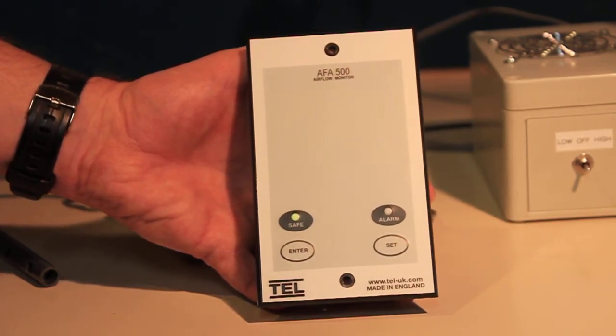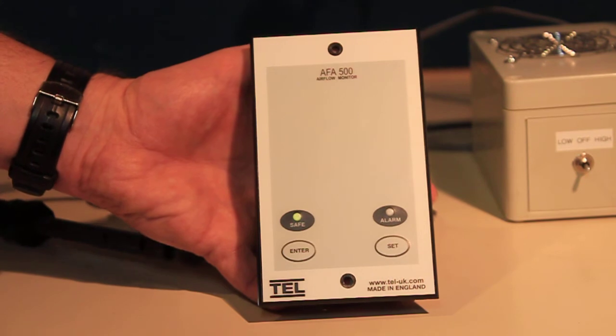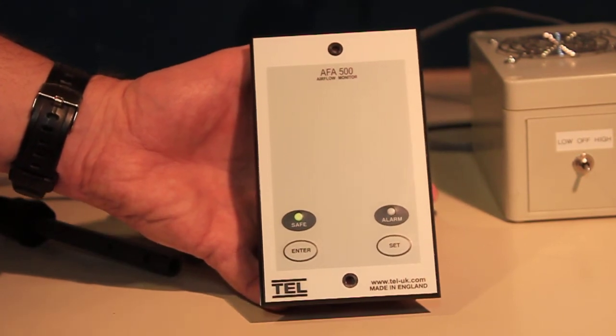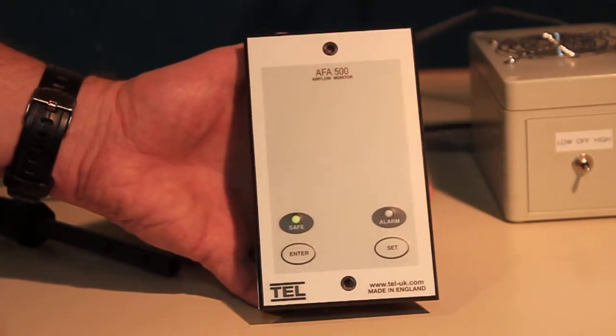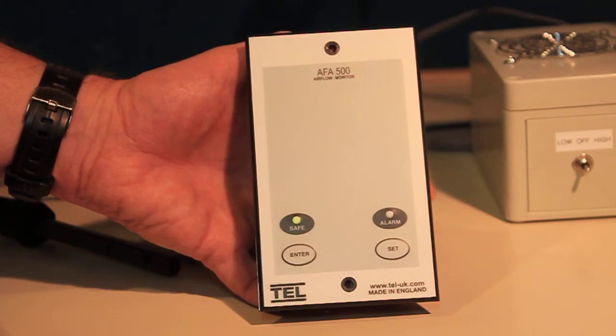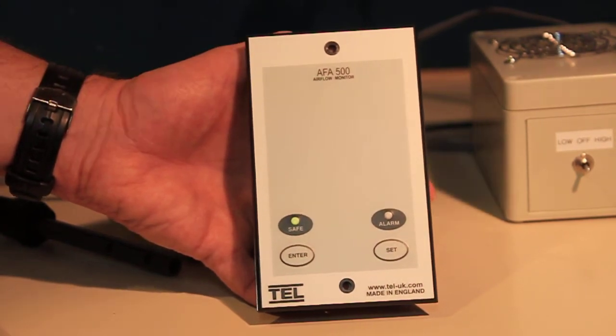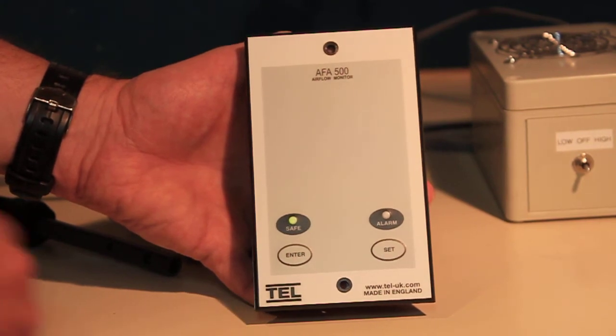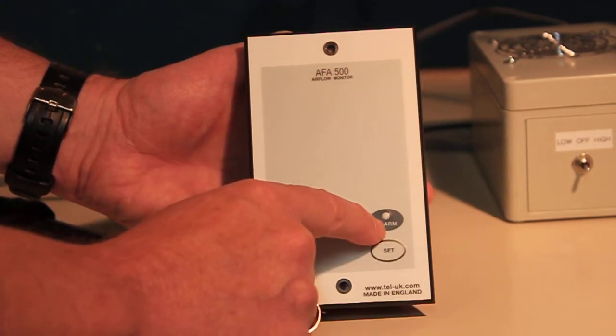If calibration is successful, the monitor will give a two-tone beep at the end of the air sample and then automatically enter run mode. The green LED should light, indicating airflow greater than the calibrated alarm point. If the airflow drops below the alarm point, the unit will go into alarm condition, with the red LED flashing and the audible horn beeping.